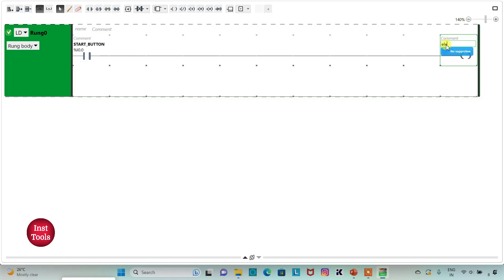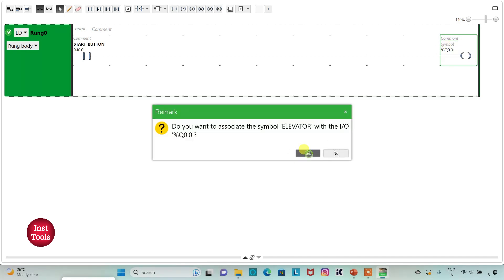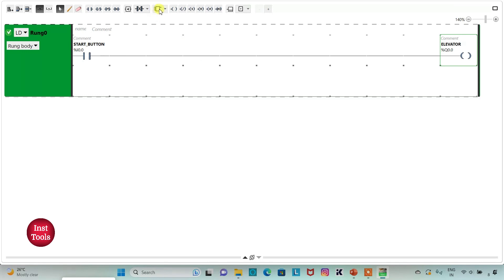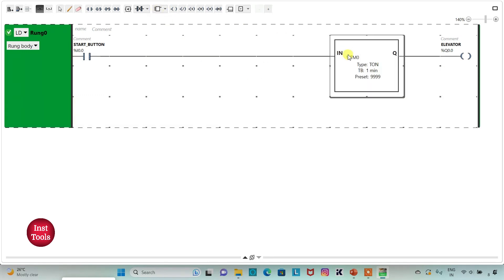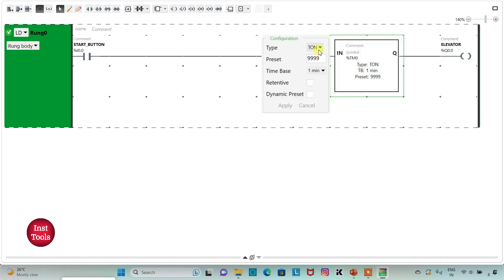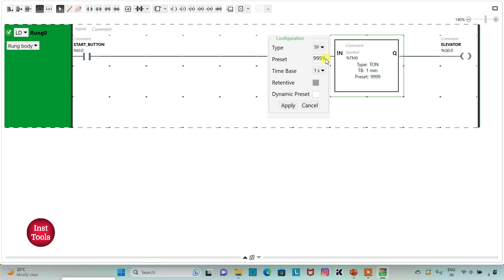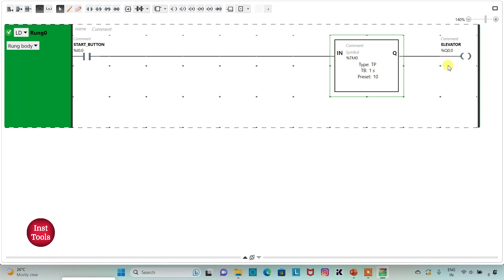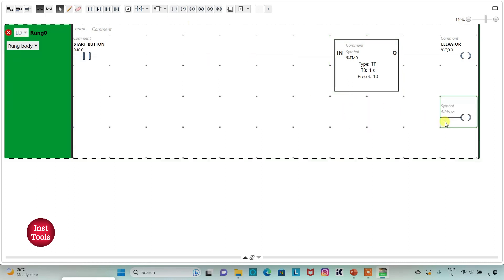Then I will insert a timer for the elevator. I will change the type to TP (Time Pulse), set time base to seconds, and preset value to 10 — so the elevator should move for 10 seconds. Then I will insert one more coil and assign address M0.